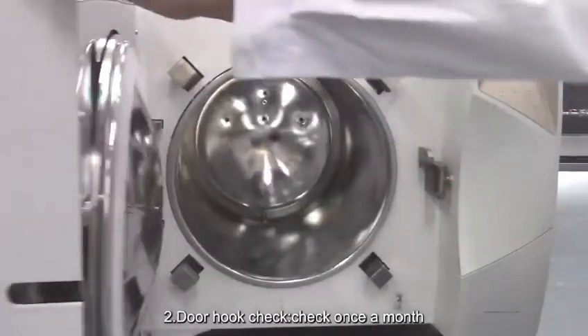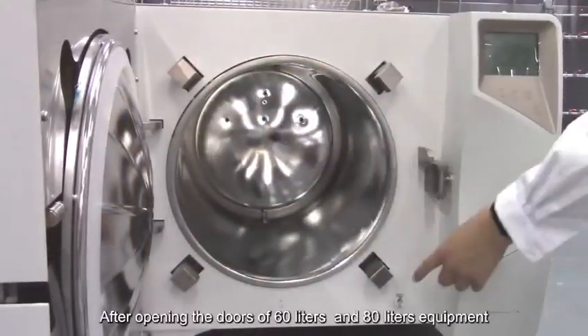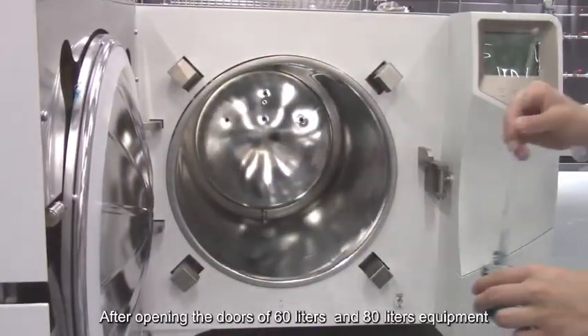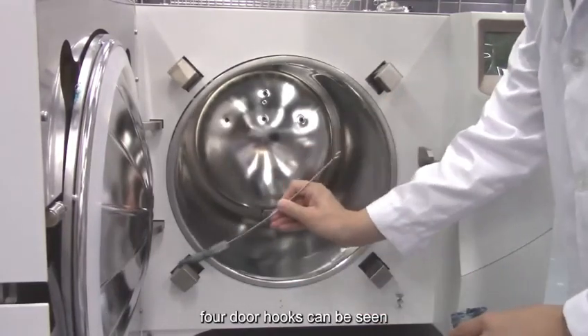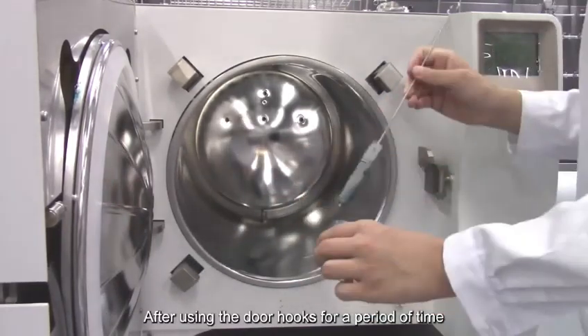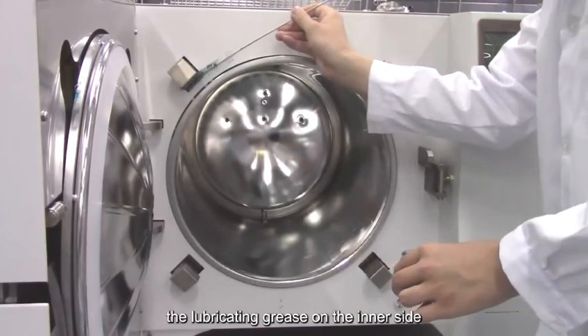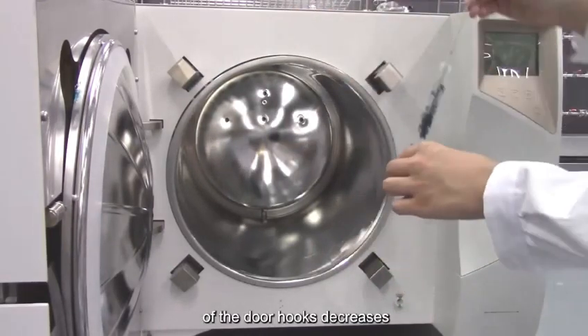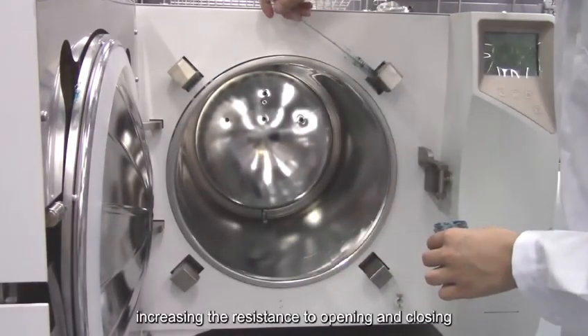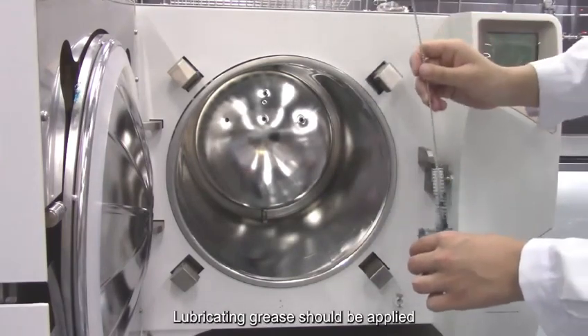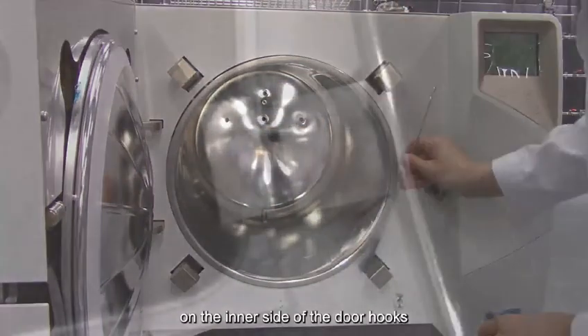Two. Door hook check. Check once a month. After opening the doors of 60 liters and 80 liters equipment, 4 door hooks can be seen. After using the door hooks for a period of time, the lubricating grease on the inner side of the door hooks decreases, increasing the resistance to opening and closing. Lubricating grease should be applied on the inner side of the door hooks.